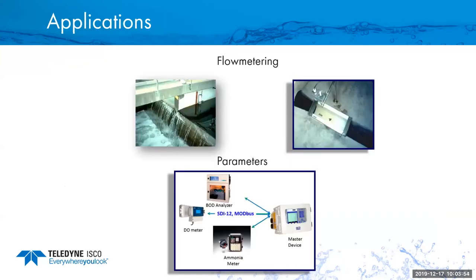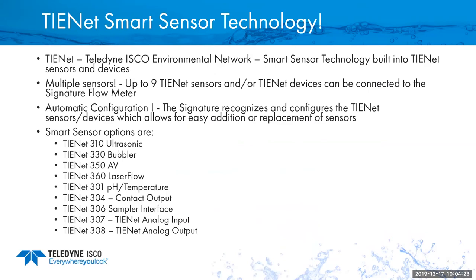Now with the applications, we'd be using flow metering or parameters. So flow metering would be using weirs, flumes, pipes, things like that to measure your flow. And then also the parameters, such as maybe a sonde to bring in pH or BOD or even DO or turbidity. Those different parameters can be brought in to the signature flow meter and stored and used for collection. The TIENet is our Teledyne ISCO environmental network, which is what we call a smart sensor. It's built into all the signature flow meters.